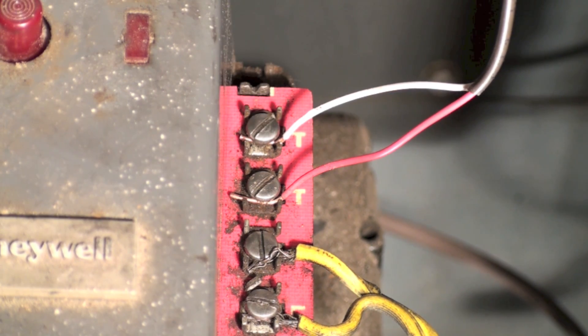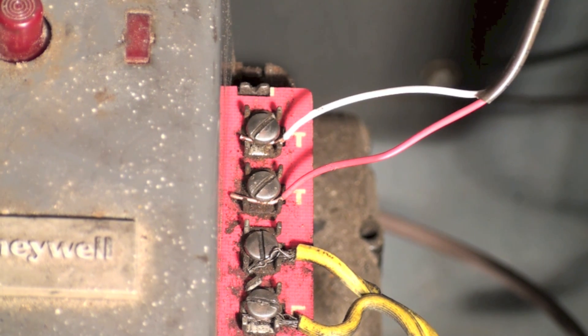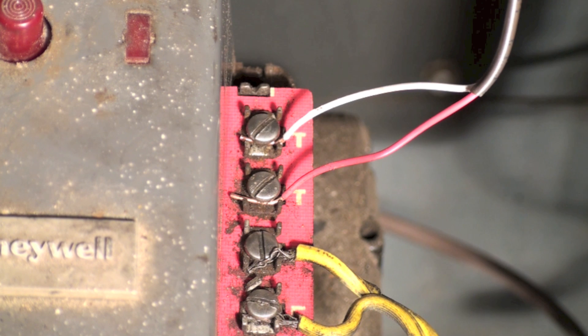To identify which wires are which, it'll usually say something like TT or something like that that are the thermostat wires, and there will only be two. If you're trying to run this with a separate power source, number one, you're going to have to come up with a transformer.